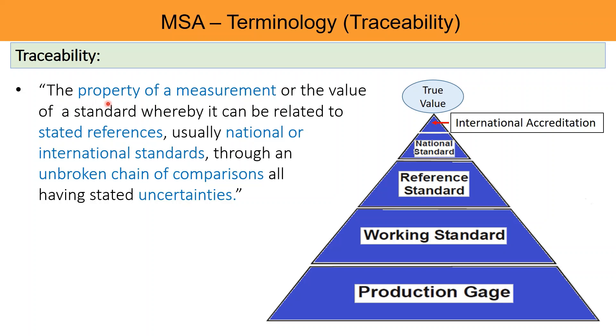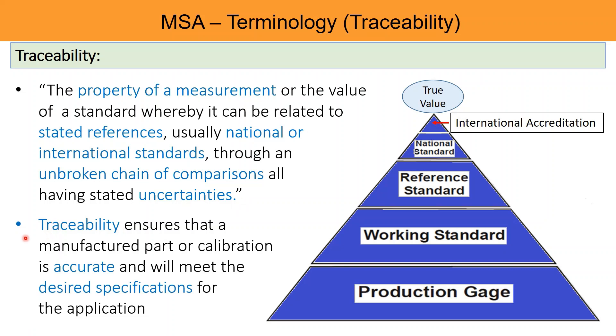Traceability is the property of a measurement or the value of a standard whereby it can be related to stated references — usually national or international standards — through an unbroken chain of comparisons, all having stated uncertainties. The purpose of traceability is to keep track of and record the history. Traceability ensures that a manufactured part or calibration is accurate and will meet the desired specifications for the application.